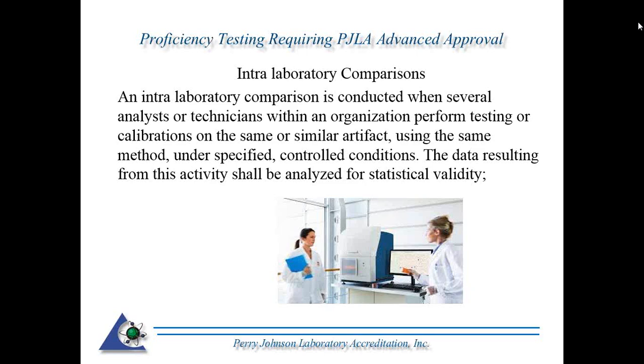Again, it's not that you're going to do an Intra-Lab. Let's say you did get approved to do a PT for an Intra-Lab. You're going to have to state in writing how you plan to conduct the test in a meaningful way and analyze the data. Again, that e-normal analysis can be used for an Intra-Lab test. You may have one senior technician, this is just an example, if you can establish your reference value and, if needed, your degree of uncertainty and compare it to other technicians within your organization. But again, that must be put into writing, why the others are not feasible and how you plan to conduct and analyze the proficiency test in a meaningful way.